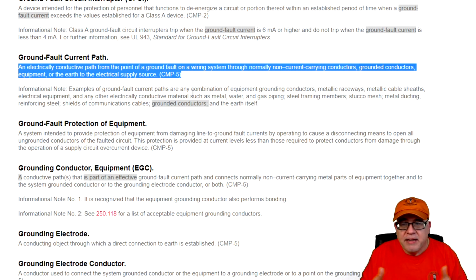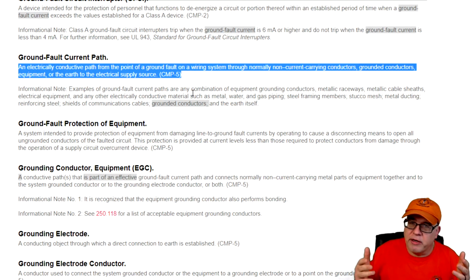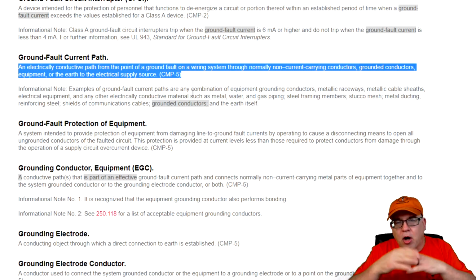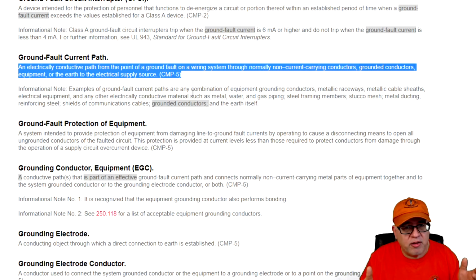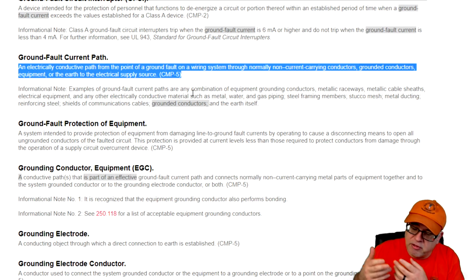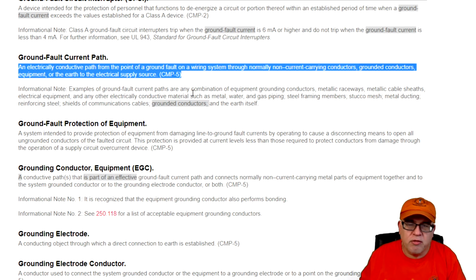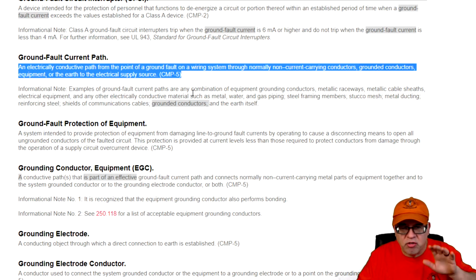It simply takes the path of least resistance, and all the current that's generated in a ground fault will take that path. It's going to take all available paths, even some with a high resistive path, and some with a low resistive path. We're trying to create the low resistance path, because more of the actual current is going to travel on the low resistive path, because it's less resistance to that current flow than on the higher. But some will take all paths. Okay, it is, again, proportional to the impedance of that path, right?